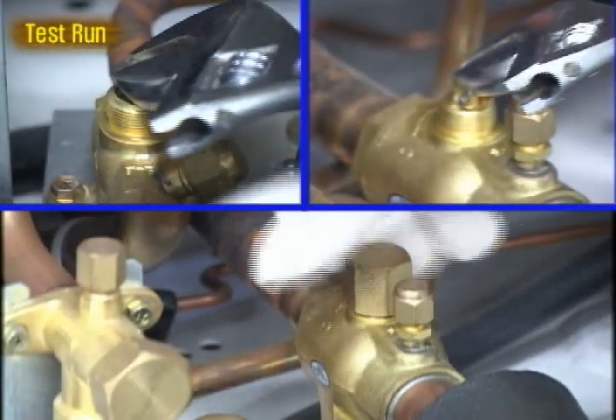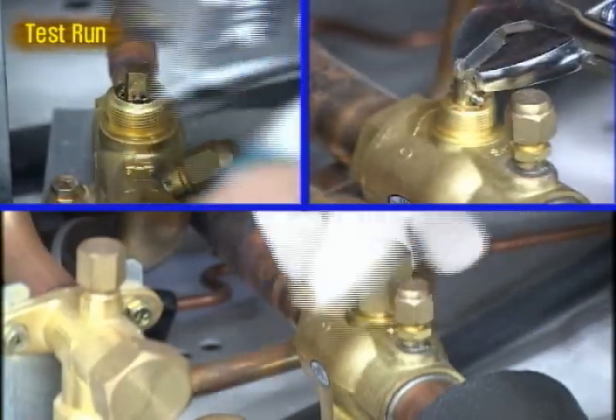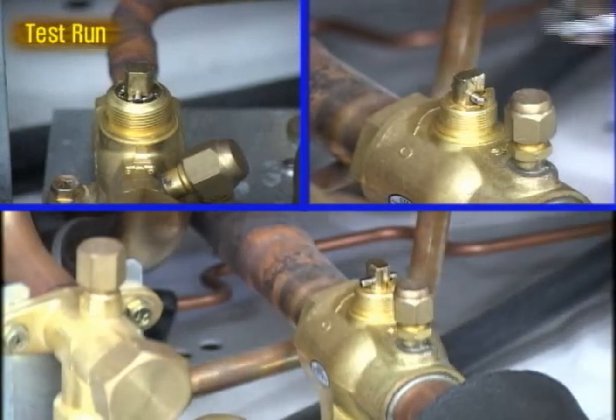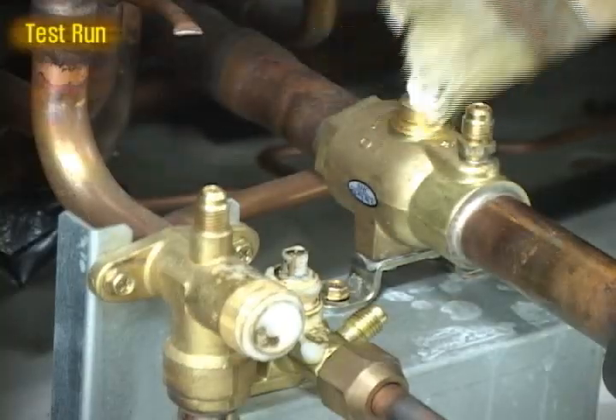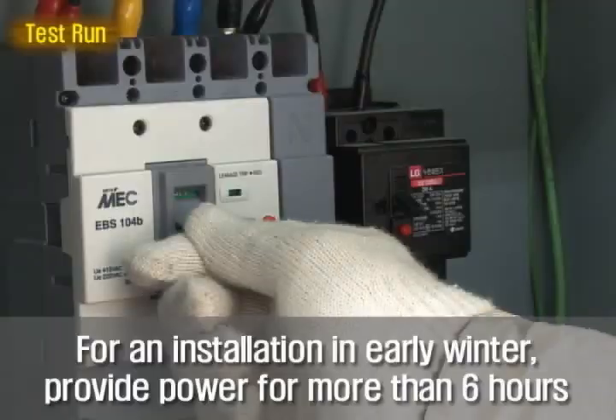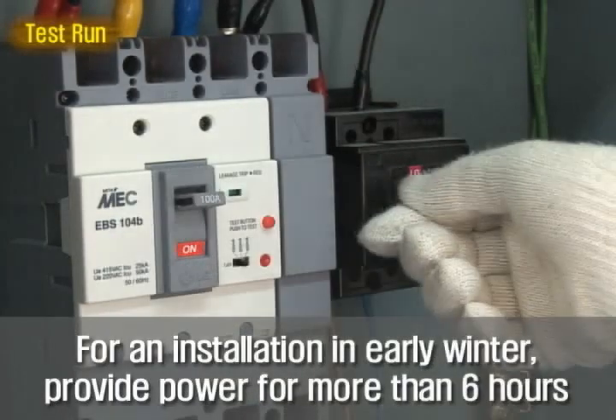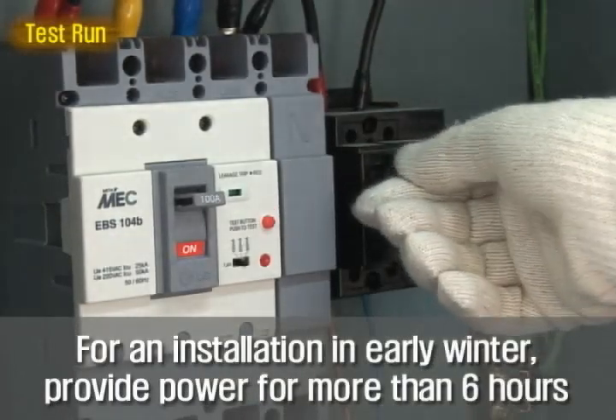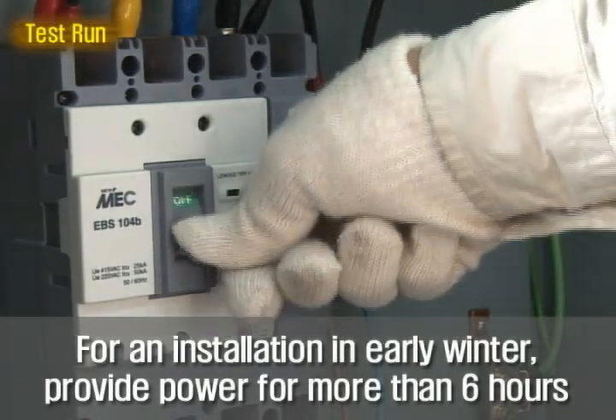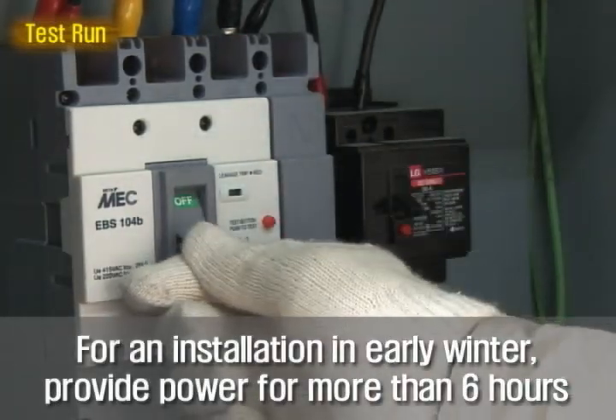If everything is ready, confirm that both service valves opened and no gas leakage occurred. Then connect the power of circuit breaker. In winter, in order to warm up the compressor heater, you must connect main power 6 hours before the operation.